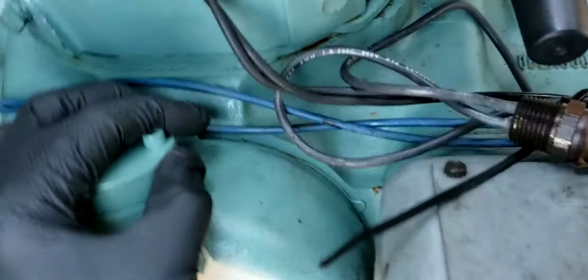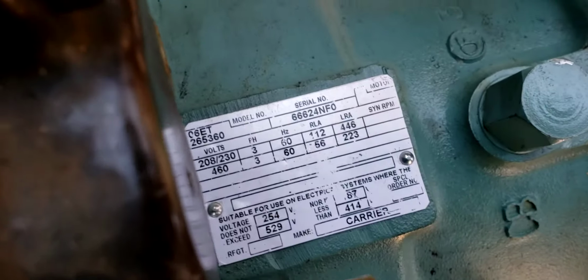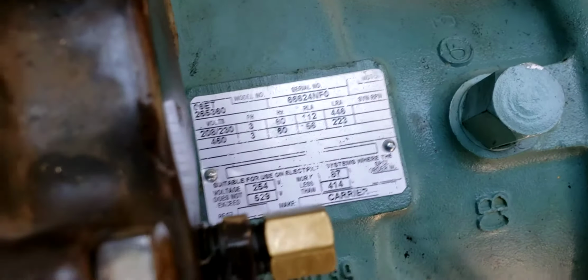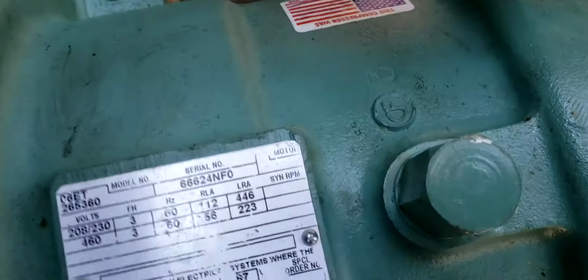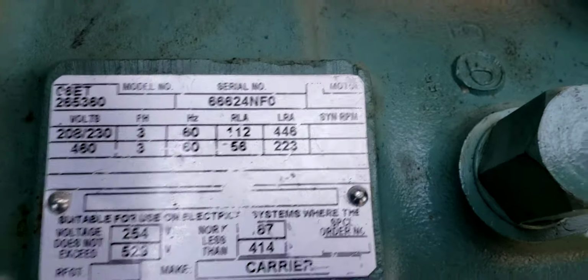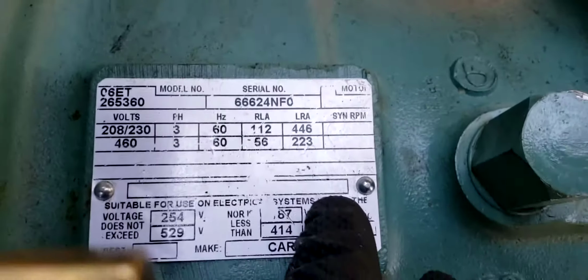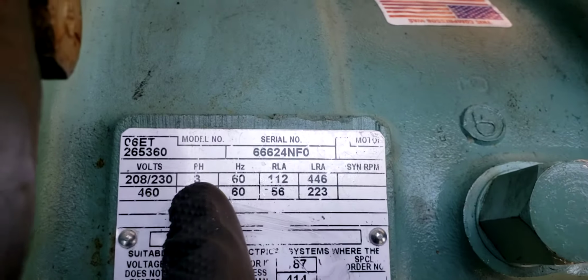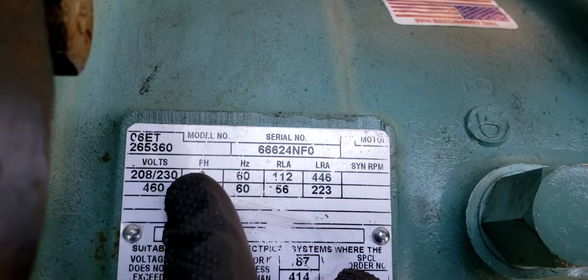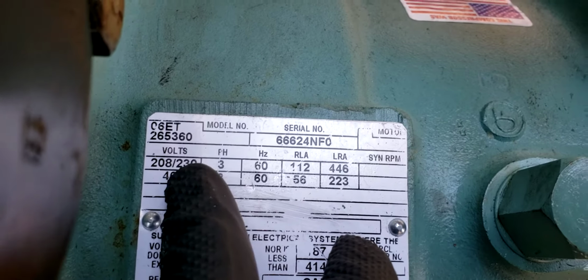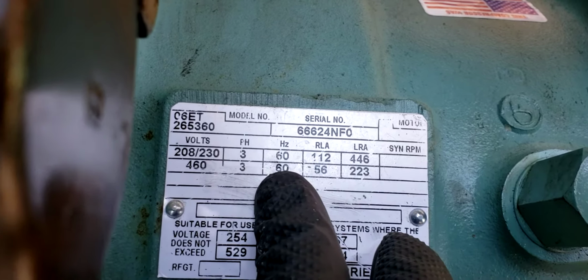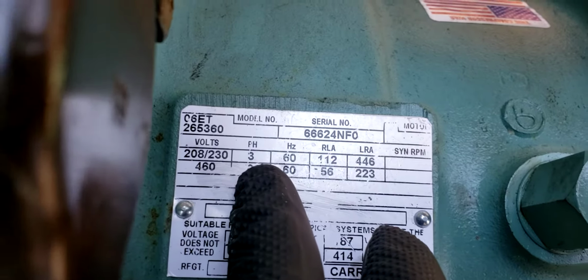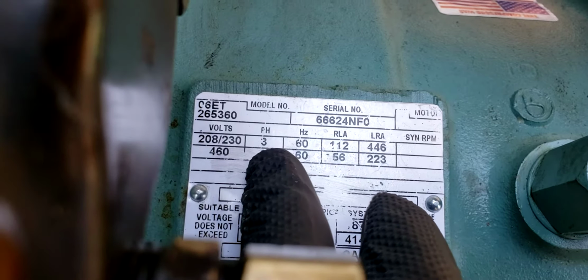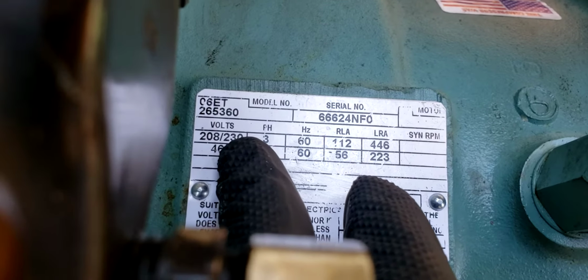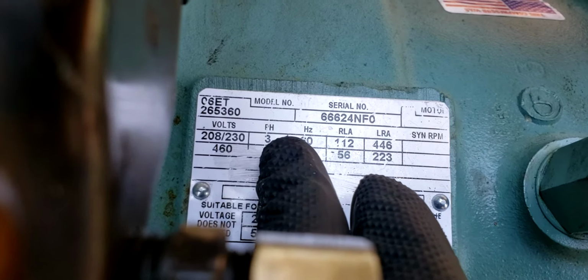Now, one thing you can do is just look at the name tag of your compressor, and it will tell you what's what. It says voltage is 230, 208, 230, and 460 volts, three phase. See right there? So obviously high voltage will be 460, and low voltage is 208 or 230.